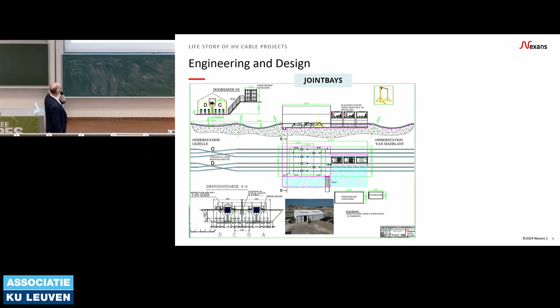It can be more complicated when you go inside tunnels, because you are not only putting your cable subsea or on land, you sometimes have to go under tunnels, and then you have to make additional studies. These have to be thermal studies, because, for example, a cable in a tunnel will heat up the tunnel, and some electronic systems inside will not work at more than 40 degrees. So you have to cool down your tunnel, sometimes making thermal studies on how to force the ventilation to cool it down, because otherwise the electrical or electronic equipment will fail.